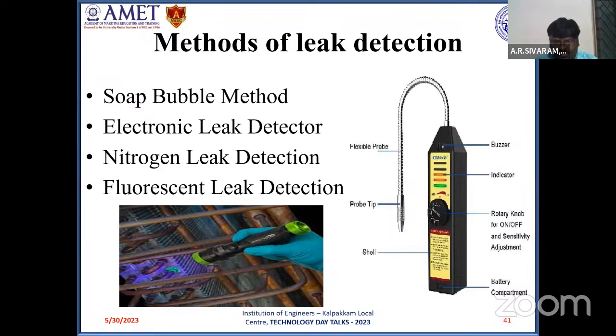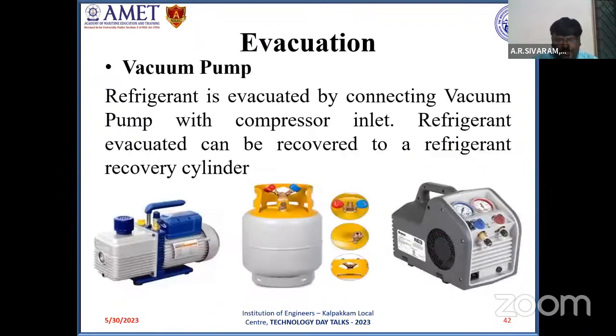And fluorescent leak detection: fluorescent dye is sent inside the system, and wherever there is a leak, you can see the working fluid and a change in color. Out of these, the soap bubble method and the electronic leak detector are widely used in commercial systems.